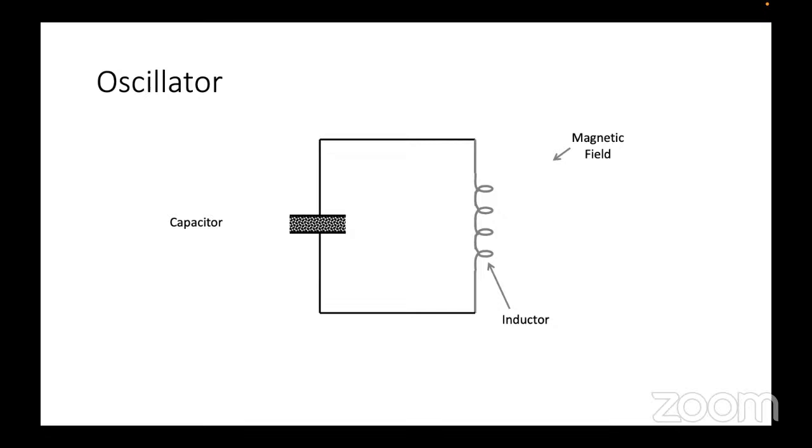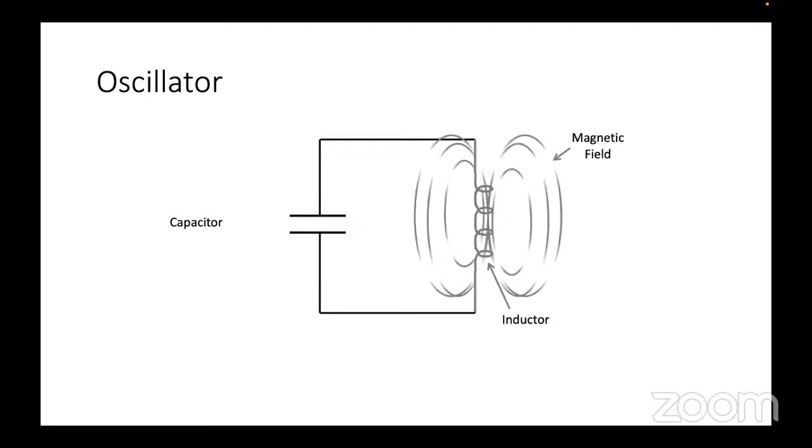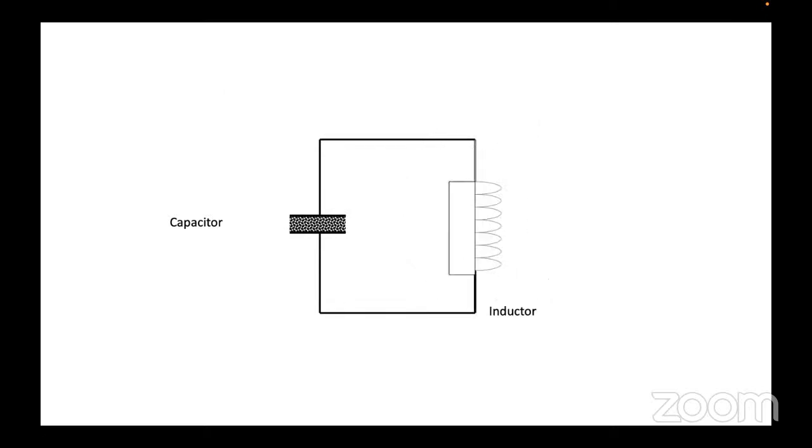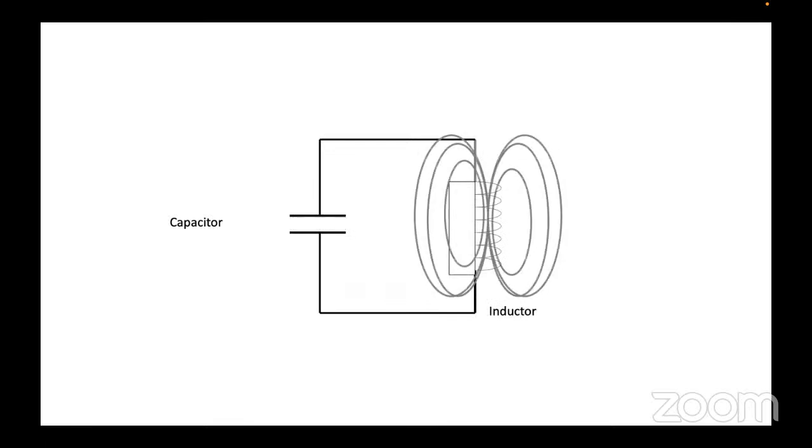So when the capacitor circuit is on, the current will flow through the inductor, and because of the alternating magnetic field, this will again charge up the capacitor. And this circuit will keep going on and on till the current completely dies. So what you're doing is increasing the duration of the energy delivered to the patient while you shock them, and this is very, very important.